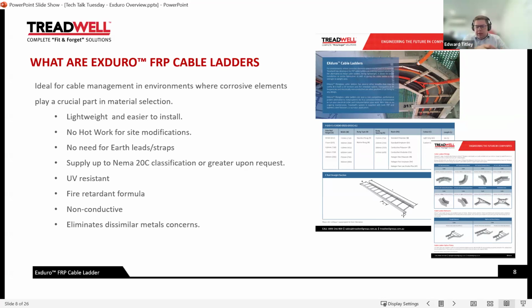Having said that, if there's a hazardous area designation, such as petroleum storage, loading facilities, ethanol, fuel, those sort of places, we can incorporate an additive to the product to give it static discharge capability. For specific surface resistivity requirements, we can add an additive to allow the product to be conductive and dissipate a static charge, so there's no risk of explosions. But as standard, it's non-conductive. We mentioned again up to NEMA 20C classification or higher on request. As FRP is what we do, we're able to provide custom or bespoke products, longer span, higher load capacities, those sort of things.